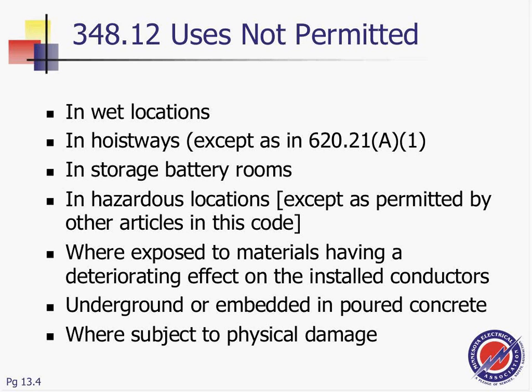And guys, they made a major change, and it's still the same in 2011, where they said you cannot use it in a wet location. So if you have a rooftop unit and you want to tie the disconnect to the rooftop unit using a flexible metallic conduit, no, you have to use Liquidtight flexible metallic conduit. That just changed in 2011, and many people have installed them outside. But in 2011, you cannot use it outside, which is a wet location.